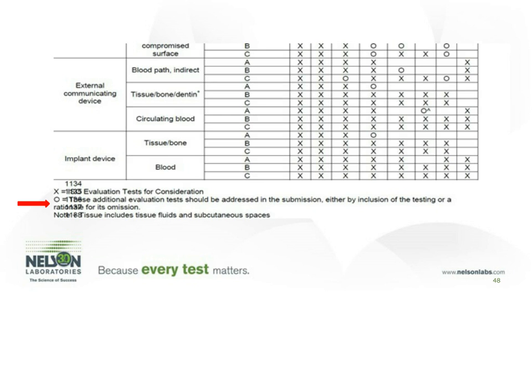And this is once again putting more emphasis on that material and chemical evaluation, where we need to know our materials, we need to know our devices, we need to know the risk that is associated to the patient, and then address those with scientific information, either through material evaluation or chemical evaluation. And only at that point, if we have gaps in our assessments, do we go to testing to answer each one of these endpoints. And so the FDA is pushing more and more away from just checkboxing and requiring individuals to be thoughtful and have a scientific approach to performing biocompatibility.